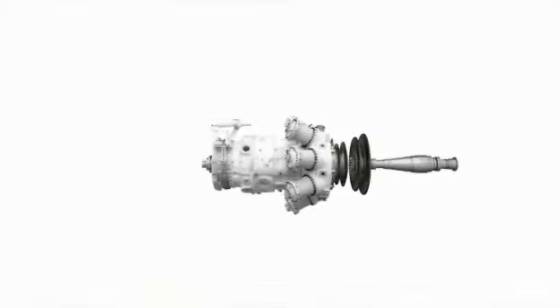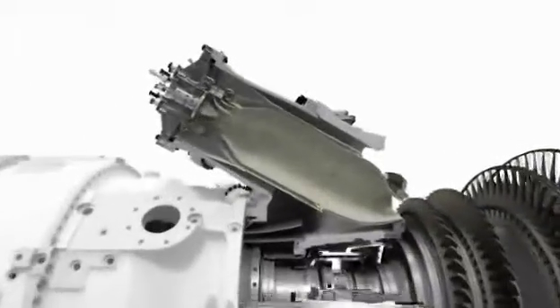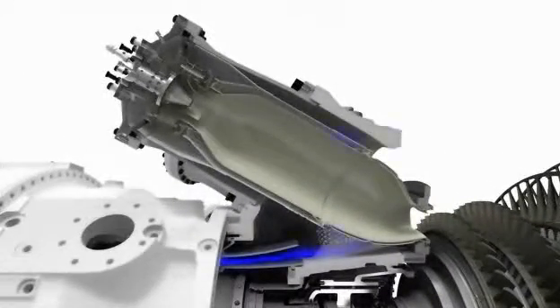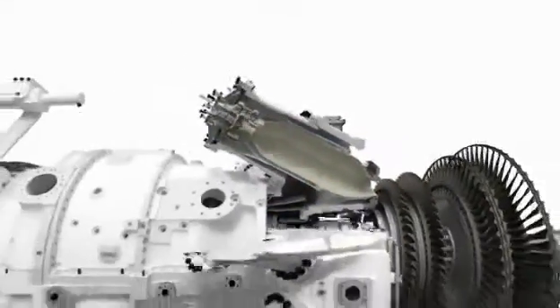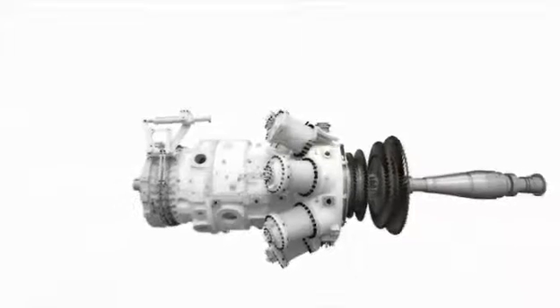DLE, Dry Low Emissions Combustion, is used in 100% of all SGT 700 and SGT 800 installations. And since 1990, it's also the standard combustion method used in the SGT 600. The DLE turndown capability enables the use of large, single turbines replacing multiple small units, allowing the same operating envelope. It offers robust and stable operation with dual fuel online switchover capabilities.